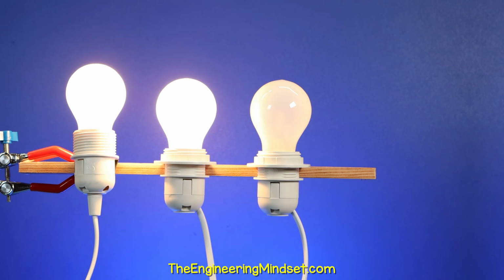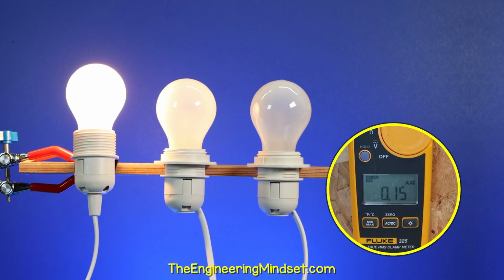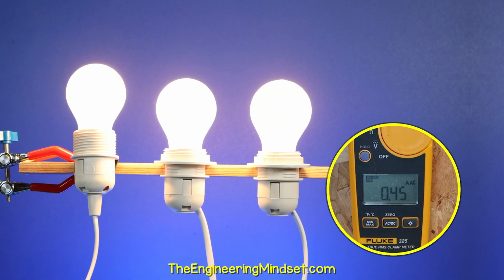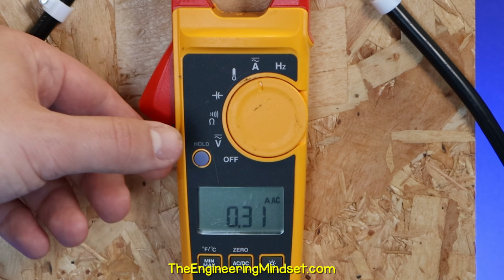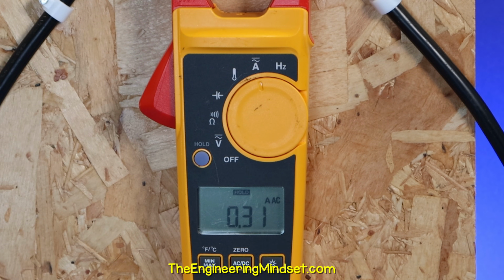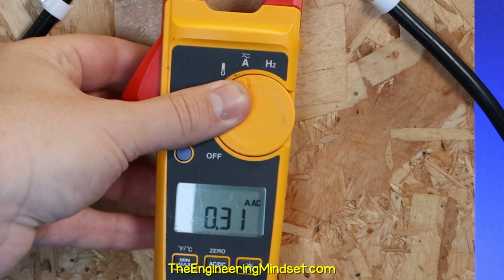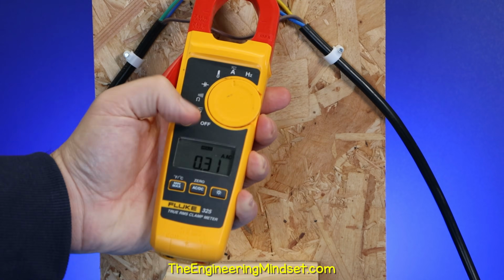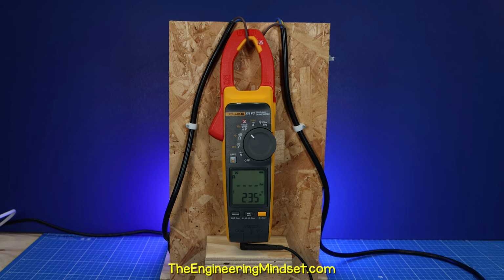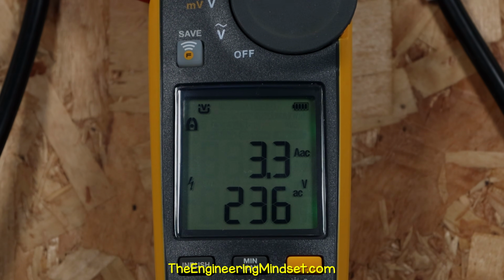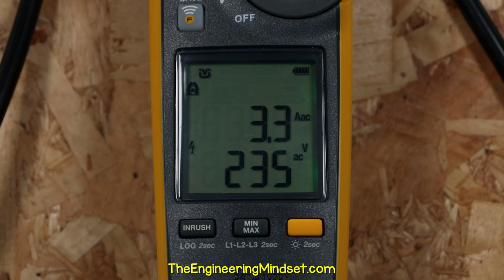If you have a varying load, we can use the minimum and maximum setting to record the highest or lowest value over a period of time. Additionally, we can press the hold button to pause the measurement on a value. We can then disconnect the meter and it will still show this value. This meter can read voltage and current at the same time through the clamp. I'll explain how later in the video.